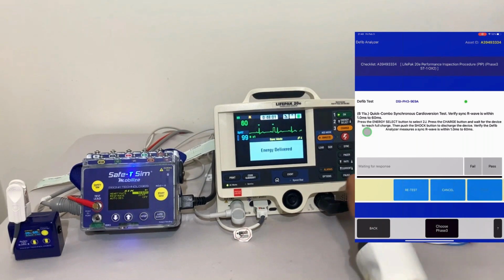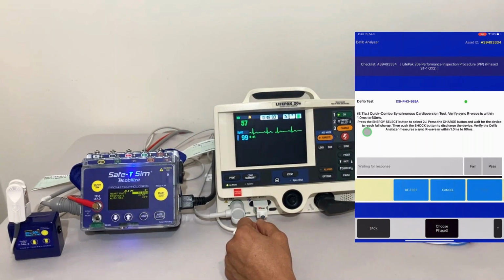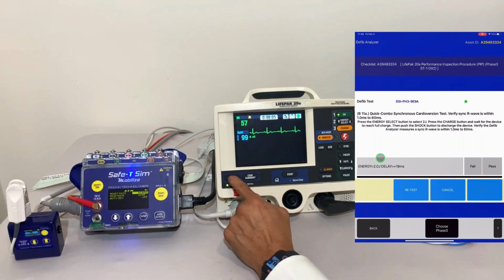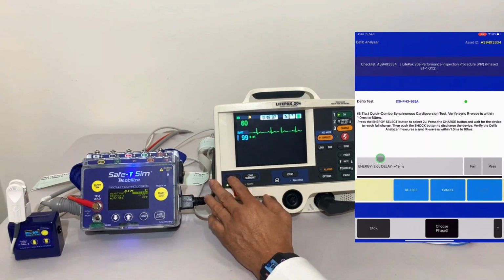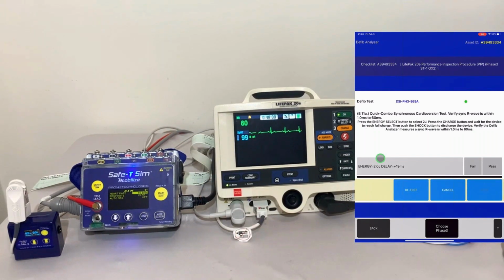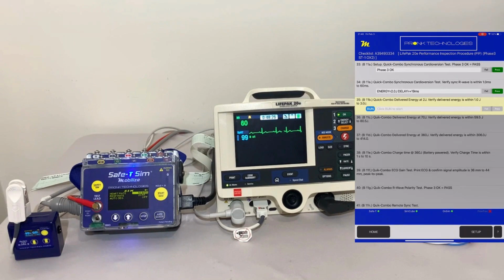And we're going to verify that our defib analyzer sends us back a result within the right range. I'm going to go ahead and stop the printer. And we can verify that the defibrillator delivered an energy of 2 joules based on our setting, and that the delay for the R wave sync was 19 milliseconds, which is well within range of 1 to 60 milliseconds. That's a pass.